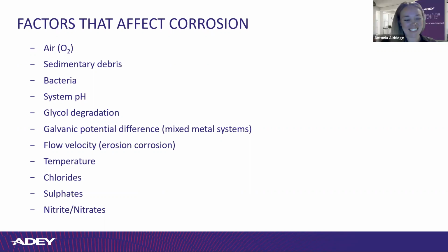But the other one you don't think about is the galvanic potential, which is galvanic corrosion, those mixed metals in the system. I did a presentation yesterday. If you guys got on here later, I had a bunch of trade school instructors in there, and their light went off on their head when they thought about this, because they know how many different kinds of metals are installed in a typical hydronic system, and that causes a sacrificial anode, and typically it's that ferrous material, so it starts breaking down and getting into all kinds of spots and causing issues.